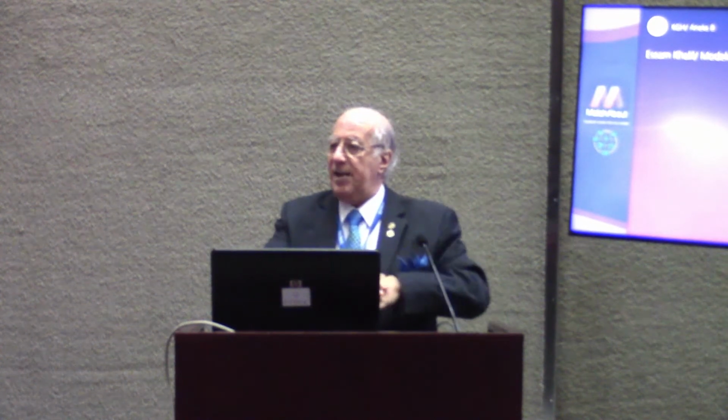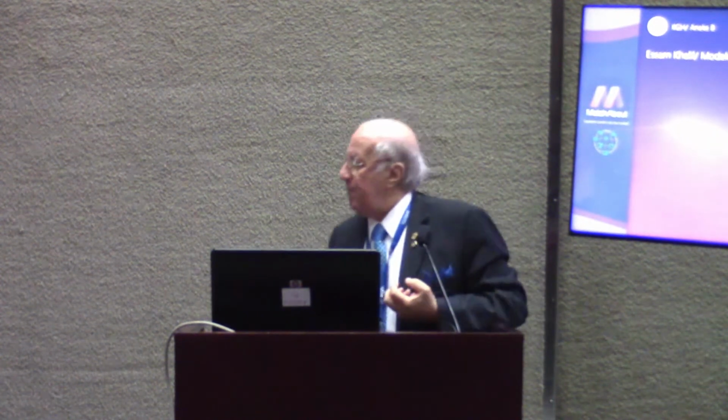Ideally, we'd like to have the air coming from the ceiling going into the floor. This will be a piston type air distribution, pushing, and there will be no pockets, no possibility of any impurities or pollution in the room. But unfortunately, in operating theaters, we have to make anti-static flooring for the doctors when they are building up charge. This electric charge has to be going somewhere, and so we have in the floor an anti-static electric network. So we cannot take the air from the underfloor. We have to take it from the sides, and for that we have different designs.